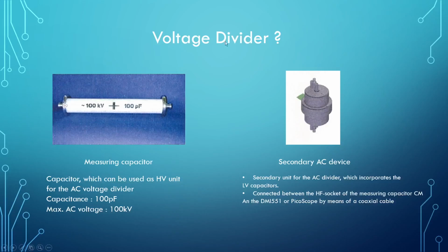Each secondary device has a different serial number, settings, and calibration value. So make sure the serial number value is the right one. This is because we need to refer to the manual book in order to obtain the divider coefficient value to set to the control system. The serial number of the secondary AC device used is 22341076-04.